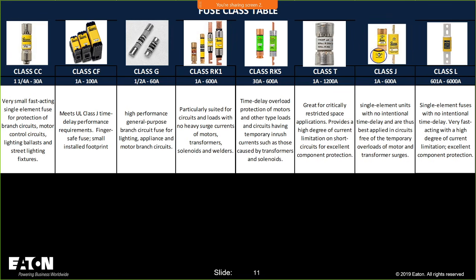Class, so we're going to walk through to help you in the way I look at things. Everybody's different. I'm going to show you my perspective on understanding all the different fuse classes and how I would determine when to use these devices and which device I would pick. So in any case, you'll see the Class L's go up to 6,000 amps. They start at 601. So remember that one question I said, which one of these class fuses are impacted by 240.67? Class T goes up to 1,200. That's the upper limit. So that one's impacted because 240.67 only applies to fuses 1,200 amps and above.